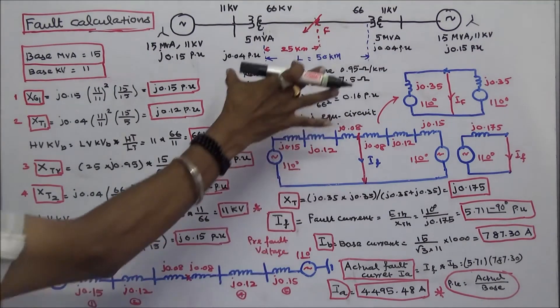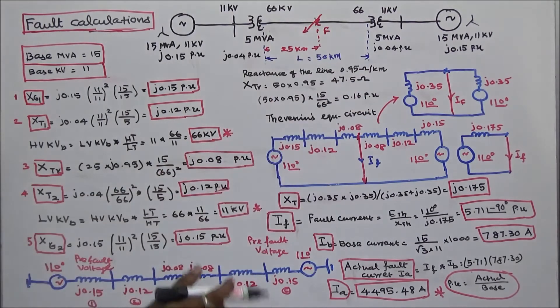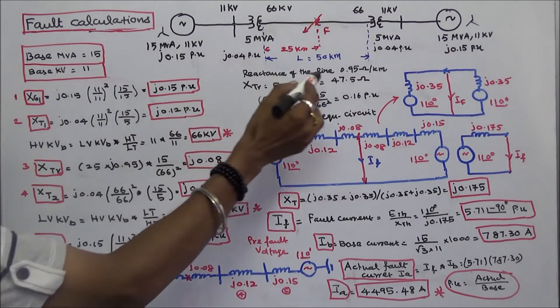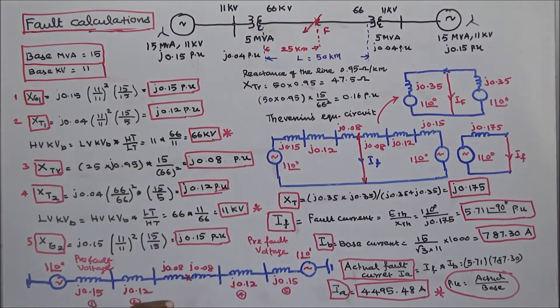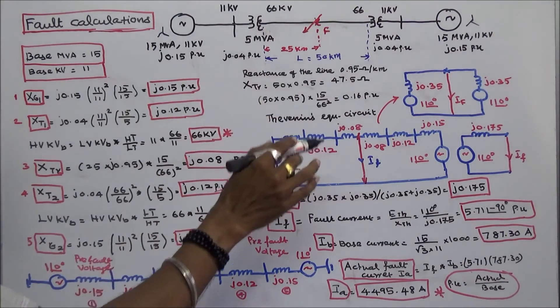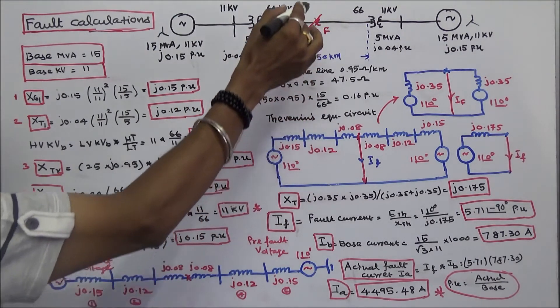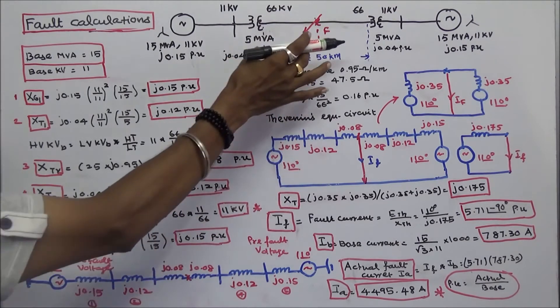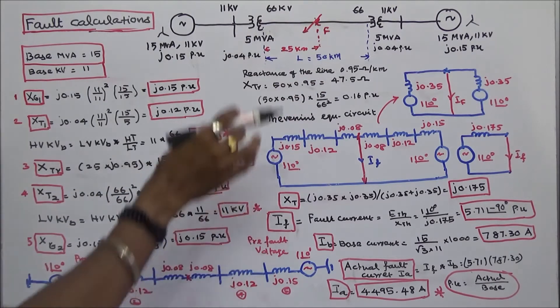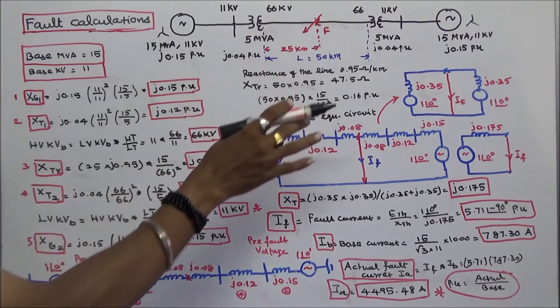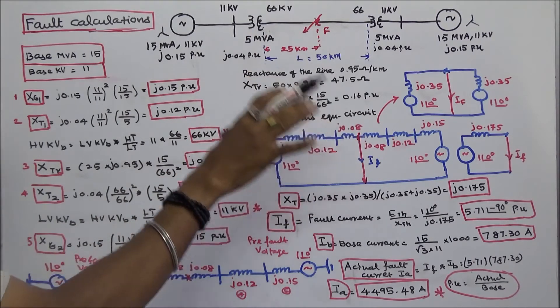The length of the transmission line is 50 km, with a reactance of 0.95 ohm per km. The question is: if a fault occurs at the midpoint of the line, that is at 25 km, calculate the per-unit fault current and the actual fault current.